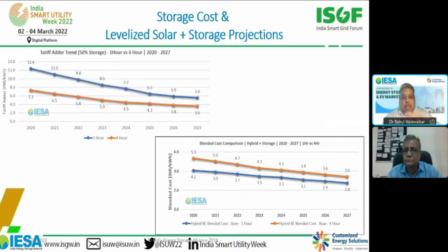And when you start looking at this, this is just one scenario, but this is a simulation we had done a couple of years back, where we had shown that in terms of the tariff adder for storage, if you are doing just 1 hour storage addition, then it actually becomes more costly because your balance of system, your inverter, your EMS and other costs get added on to just 1 hour of storage. But if you are doing a 4 hour storage, then all that cost gets divided across the 4 hours of storage.